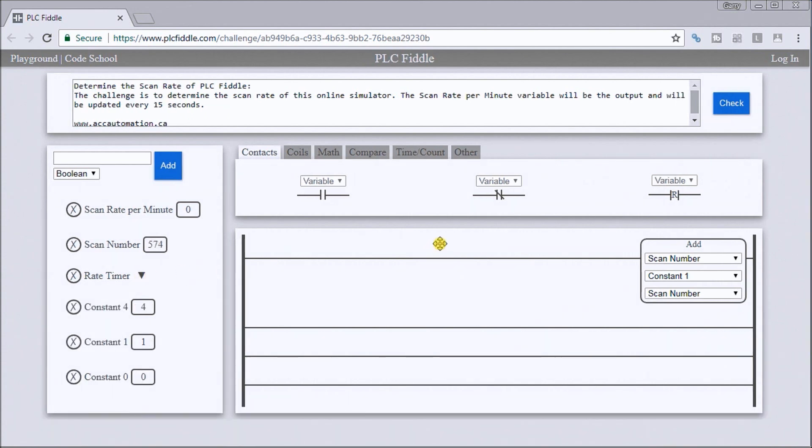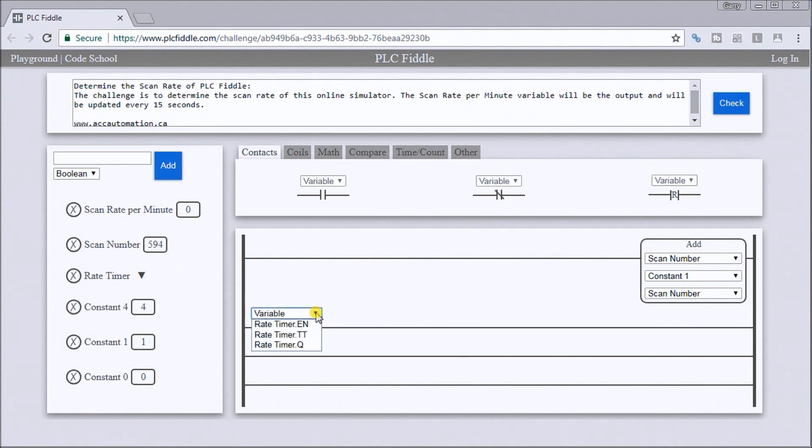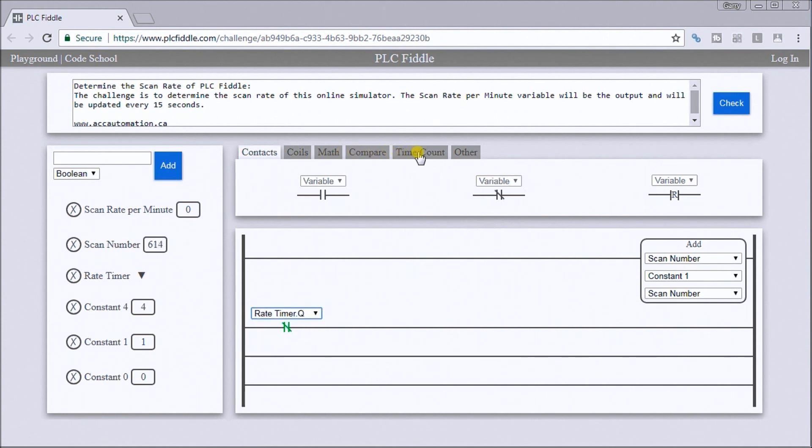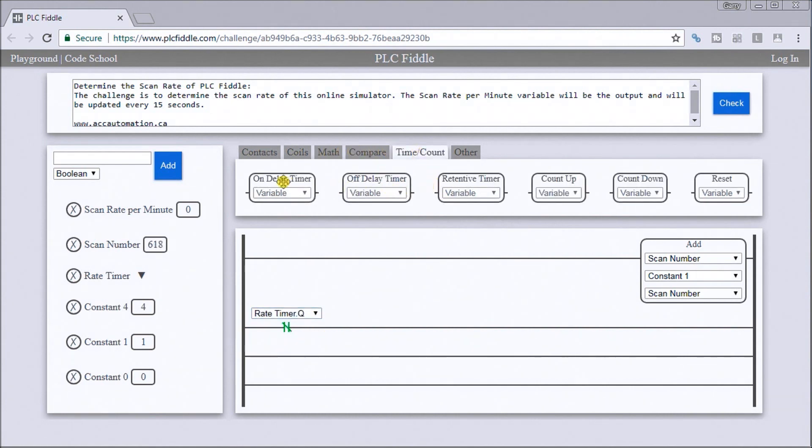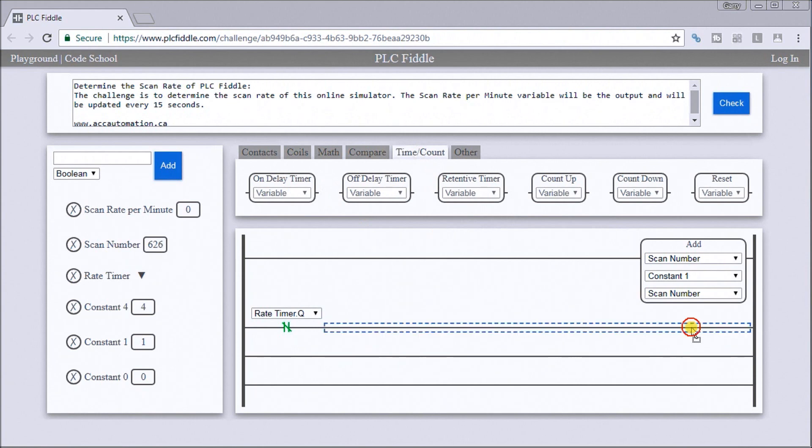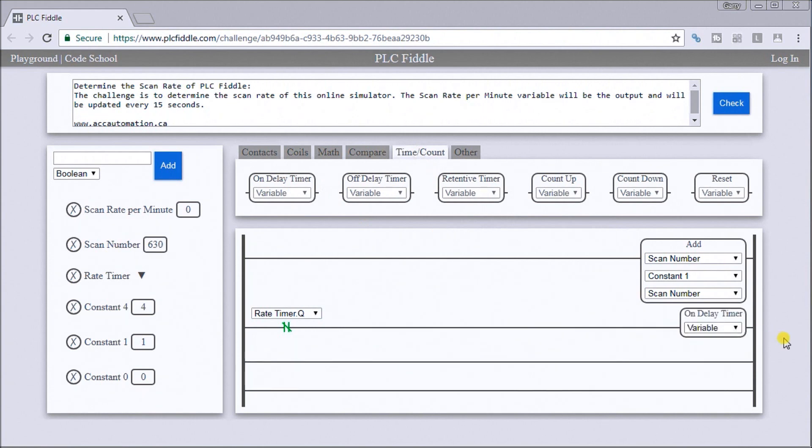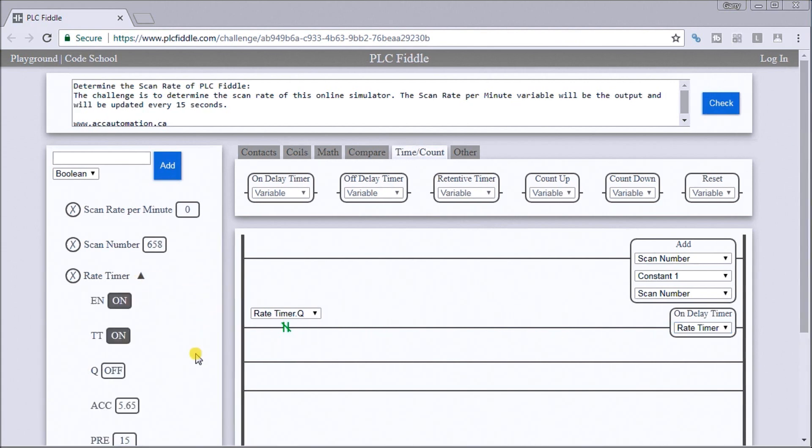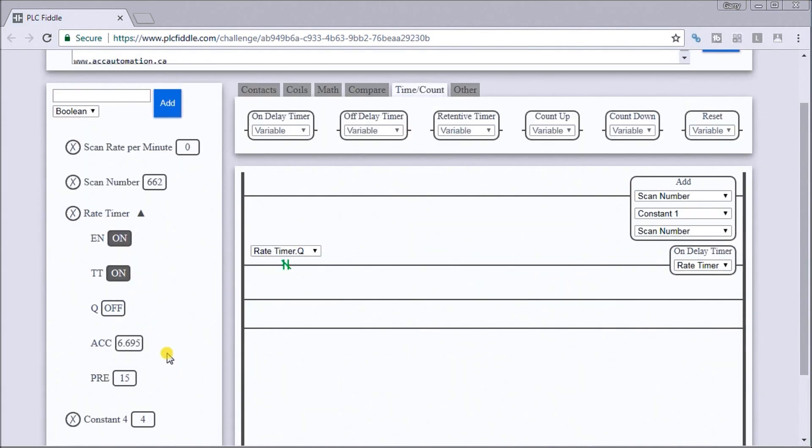The first thing we'll do is say when it's not the finish of the scan rate output, then we want the scan rate. Let's go to timer, do an on delay timer here, and we'll put that as a rate timer. Basically that's giving me every 15 seconds we're going to be updating or zeroing it out. It's just giving me a pulse over 15 seconds to do something.